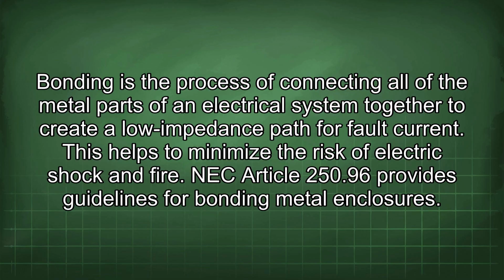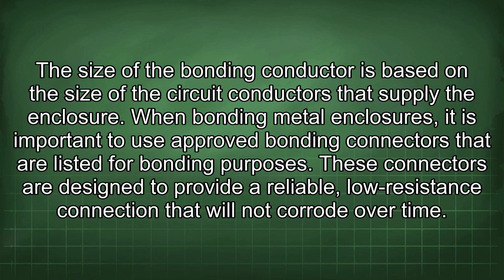NEC Article 250.96 provides guidelines for bonding metal enclosures. The size of the bonding conductor is based on the size of the circuit conductors that supply the enclosure. When bonding metal enclosures, it is important to use approved bonding connectors that are listed for bonding purposes. These connectors are designed to provide a reliable, low-resistance connection that will not corrode over time.